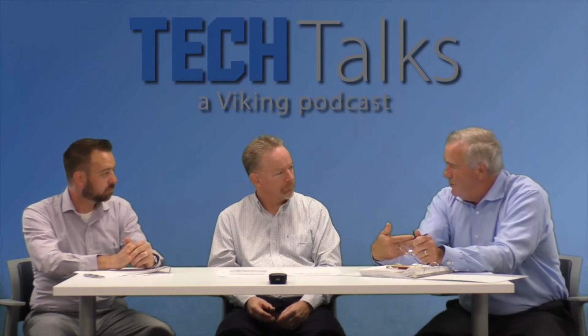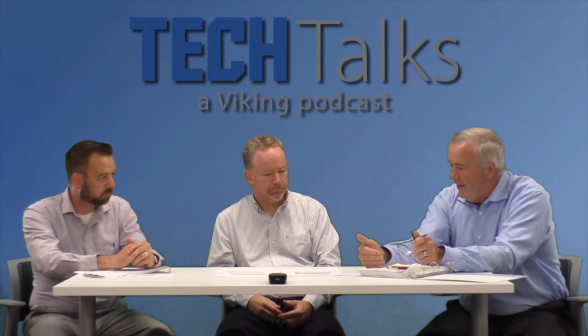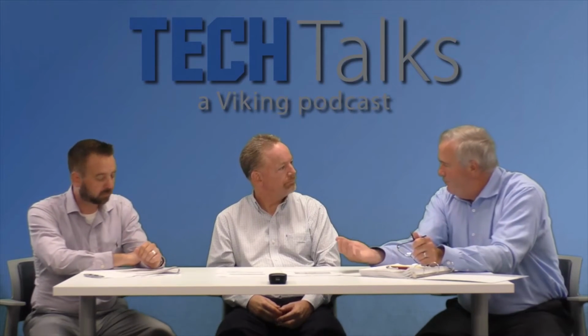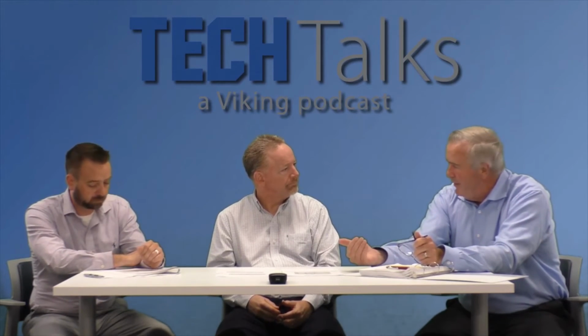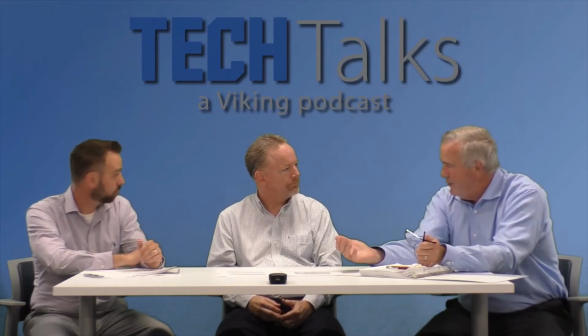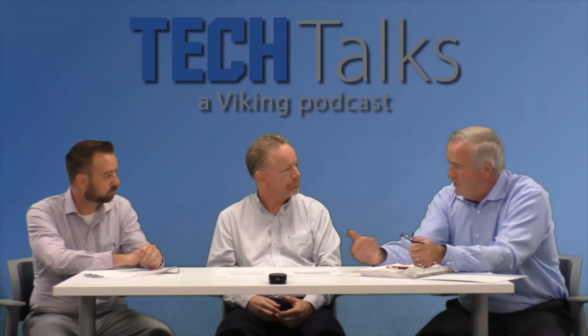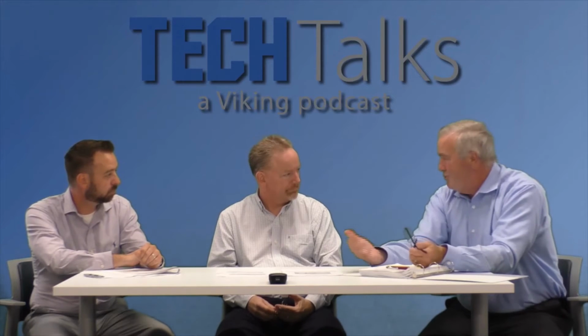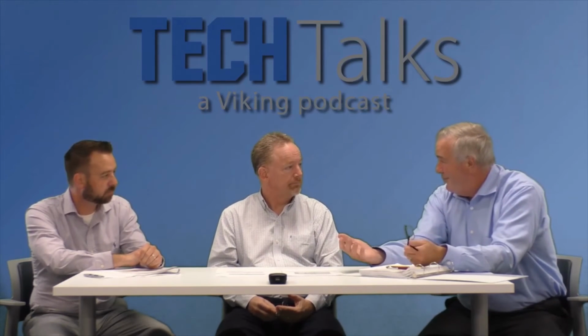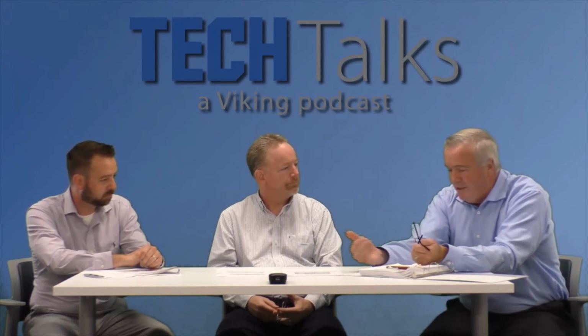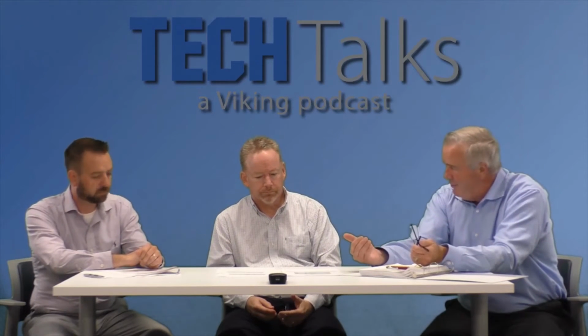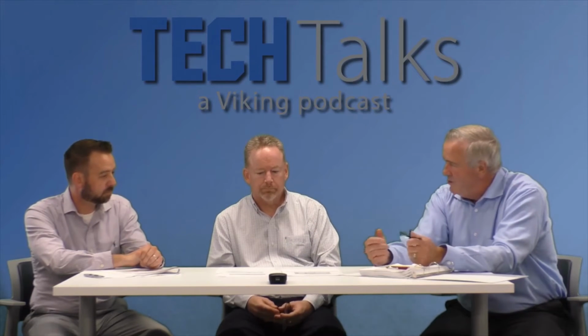So we have a 9 sprinkler design at 50-foot ceilings, and then we have a 9 and a 10 sprinkler design. What you do is calculate 9, verifying the first 4 will discharge at 80 PSI, and you could stay at 9. You don't have to go to 10. Right. If you don't have 80 PSI with the first 4 sprinklers, which you should because it's a default if you're doing the hydraulics, then you'd have to go to a 10 sprinkler design. But we tell most people you're going to have the 80 PSI, so work with the 9 sprinkler design at the 55-foot.